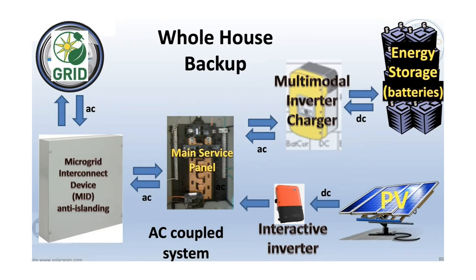And one of the things that we've been seeing more of lately is these microgrid interconnect devices. And it's kind of neat. We actually had this function inside of our multimode inverter all the time, but we took that function out of the multimode inverter and put it in a separate place. It's kind of neat when you're doing AC coupling to have this. The microgrid interconnect device, though, has to be able to talk to this multimode inverter to tell it to go into standalone mode, to go into interactive mode, and all that. So that's a microgrid interconnect device. It's sort of like an automatic transfer switch, but it has the ability to talk to this inverter to tell it what to do. And we don't call it an automatic transfer switch because the code has better benefits for us when we call it a microgrid interconnect device, or an MID.